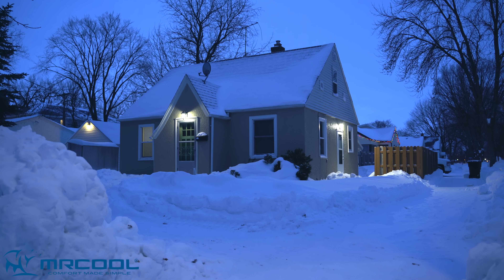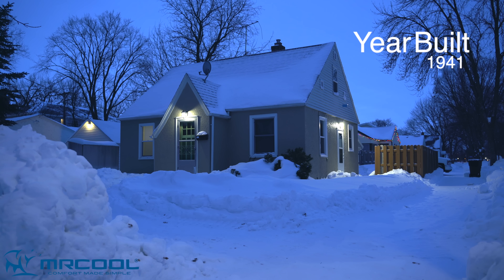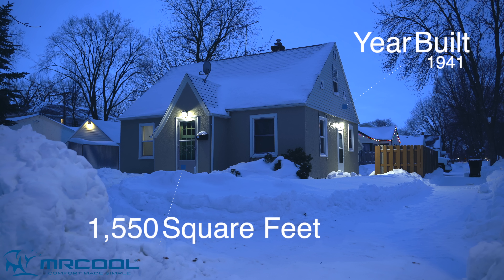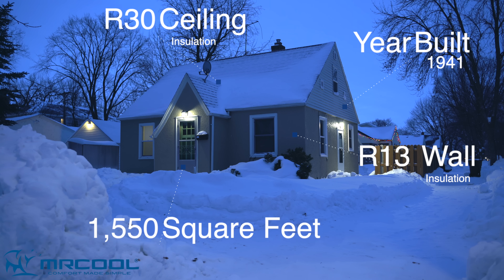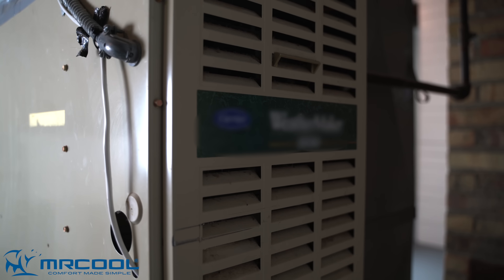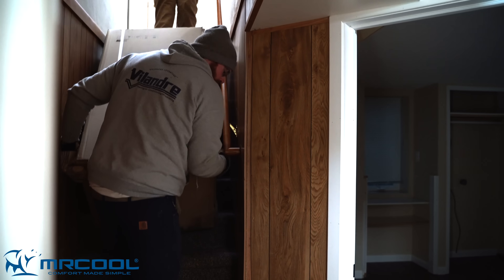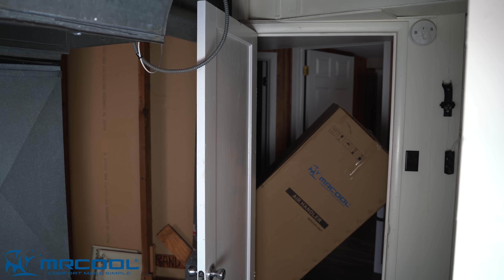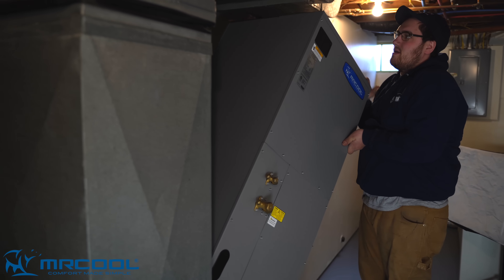The house where we installed the unit is located just off of North 25th Street. Built in 1941, this house is about 1,500 square feet with R13 insulation in the walls and R30 insulation in the ceiling. We replaced a gas furnace with a two to three ton Mr. Cool Universal heat pump. This particular unit works as an upflow and horizontal system. We also did not install an auxiliary heat strip, just so we could see how well it would perform.